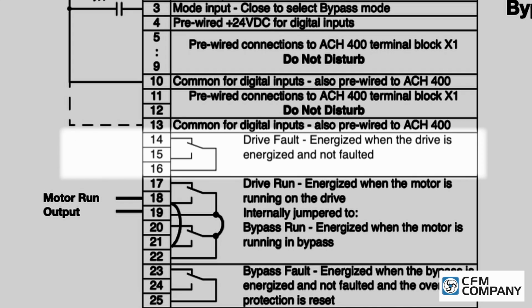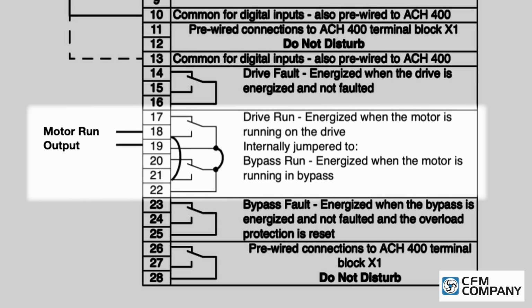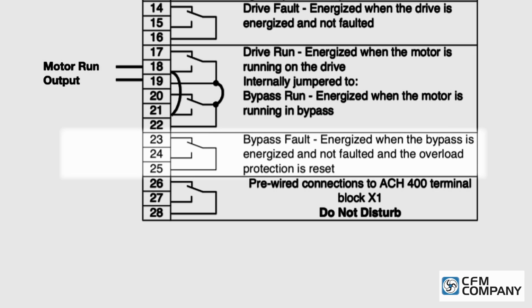Relay 1, terminals 14, 15, and 16 is the drive fault relay. This relay is energized when the drive is energized and when the drive is not in fault. Relay 2, terminals 17, 18, and 19 is the drive run relay. It is wired in parallel with Relay 3, terminals 20, 21, and 22, the bypass run relay. Together, these 2 relays provide the motor run status. Relay 4, terminals 23, 24, and 25 is the bypass fault relay. This relay is energized when the bypass is not in fault and the overload protection is reset.